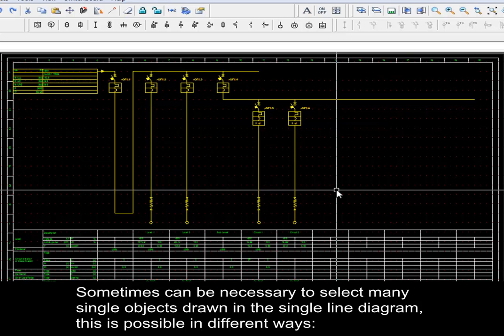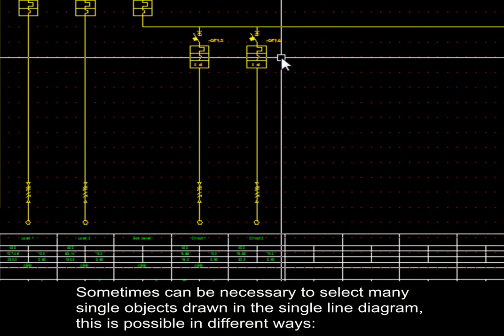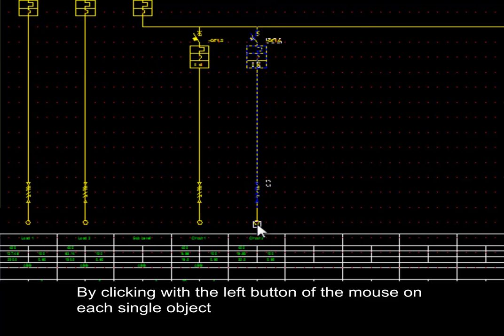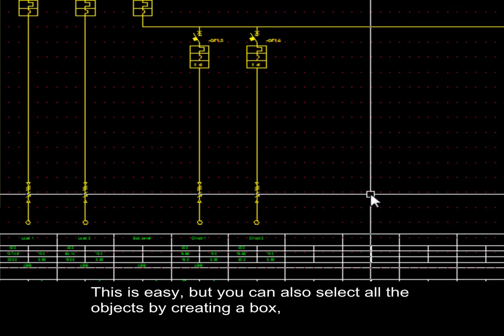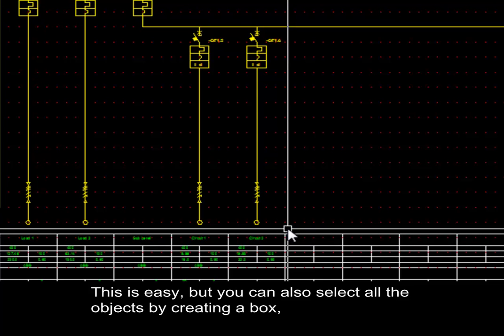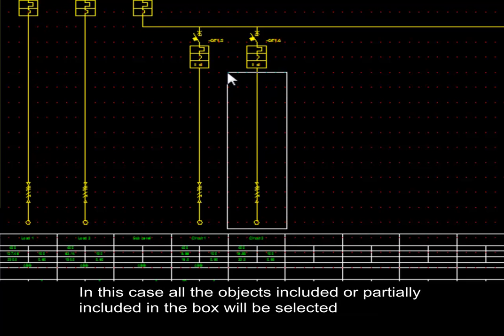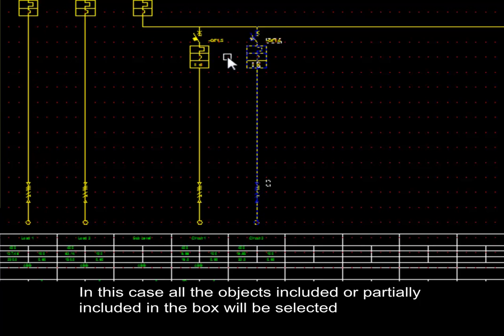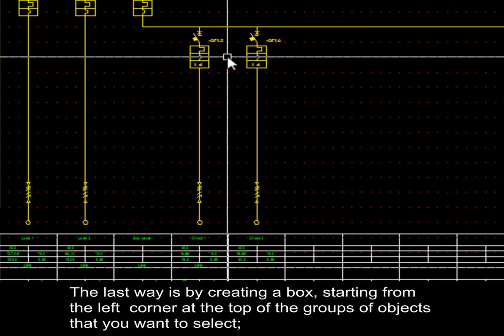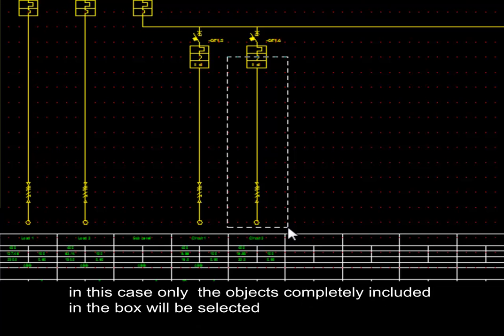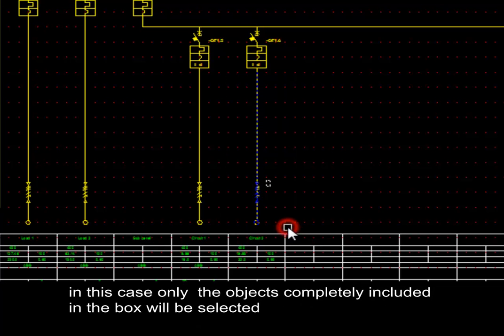Sometimes it is necessary to select many objects in the single line diagram. This can be done in different ways: clicking the left mouse button on each single object; creating a selection box starting from the right corner at the bottom — all objects included or partially included will be selected; or creating a box starting from the left corner at the top — in this case only objects completely included in the box will be selected.